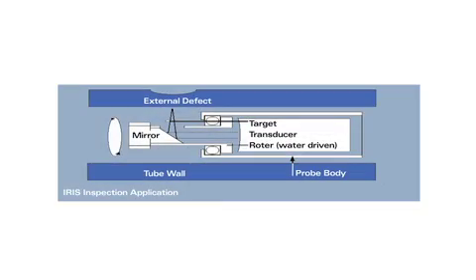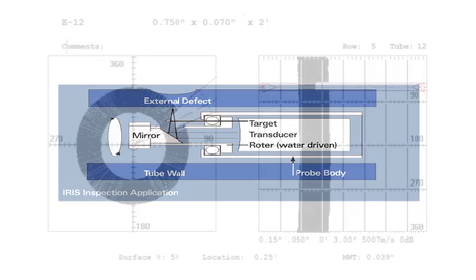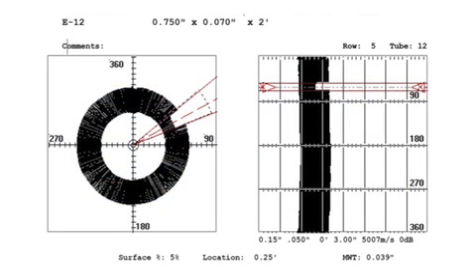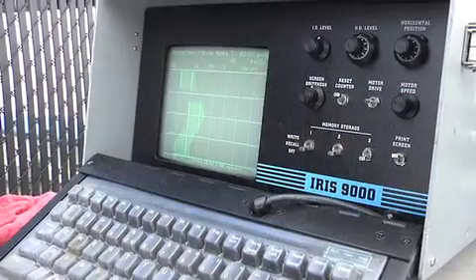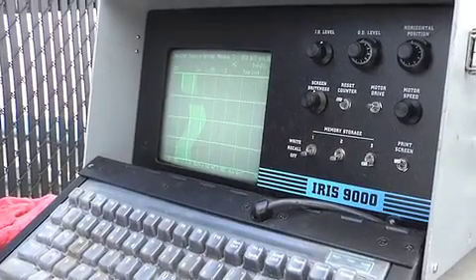The transducer emits the signal. There's a 45-degree mirror that the signal reflects from, travels through the water to the tube wall. Once you hit the tube wall, this signal maps out the tube wall in the form of a B-scan. This is a defect-free area.